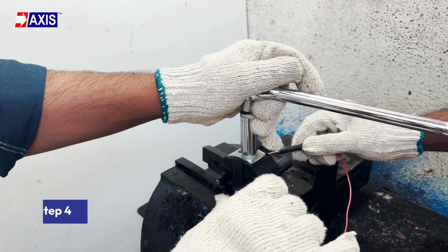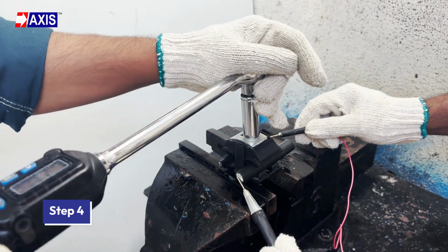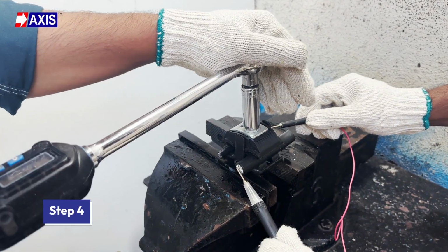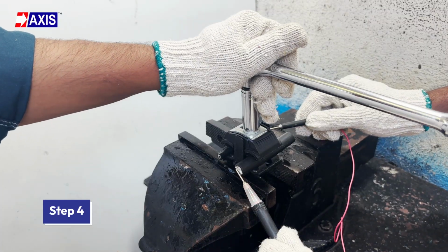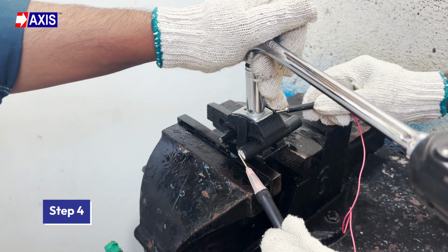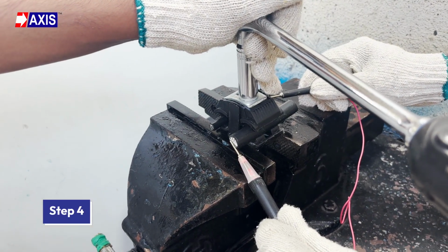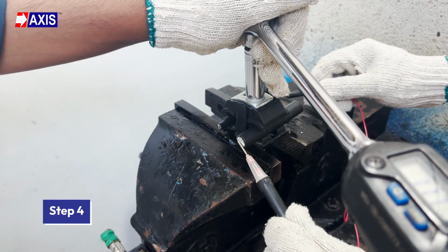Step 4. Measure the electrical continuity between the main and branch conductors. Record the torque at which continuity is achieved. This confirms that the IPC can establish a proper electrical path even when frozen.